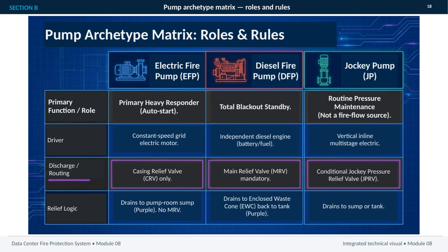This matrix distinguishes the 3 pump archetypes by role, driver, relief logic, and discharge routing. The electric fire pump, or EFP, is the primary heavy responder and auto-starts when fire flow demand requires it. It uses a constant speed grid electric motor, with only a casing relief valve, or CRV. Its discharge drains to the pump room sump, shown in purple, and does not use a main relief valve.